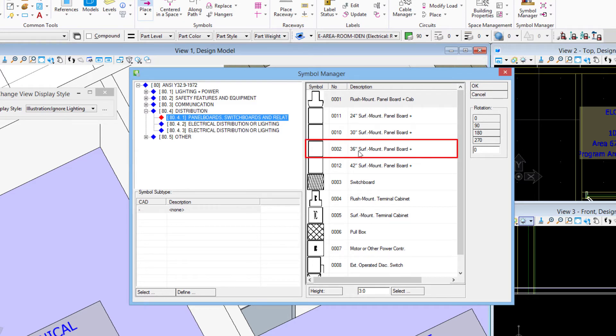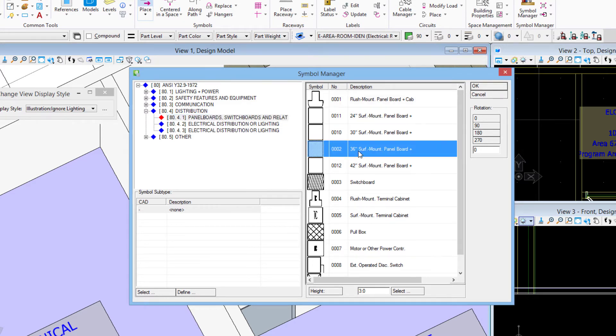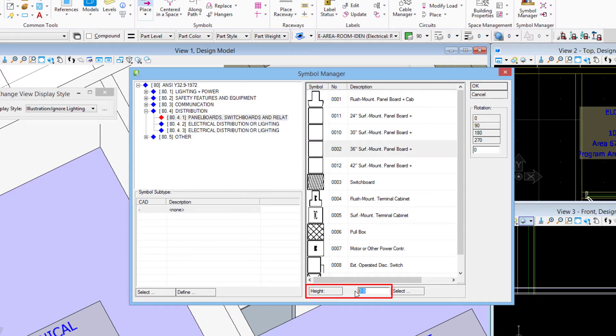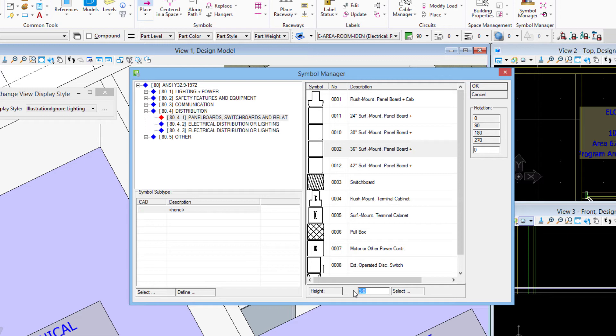You see over on the right now the different symbols available from that group. I'm going to choose this 36 inch surface mounted panel board, so we'll highlight it over here in the list. I'm setting my height setting down here to three feet. The name of this panel board - the 36 inches - that's part of the name, but that's indicating to me that it's 36 inches tall. And then the height setting is where I set the bottom location of the panel offset from the floor on this floor that I'm working on. So I'll set okay right here.